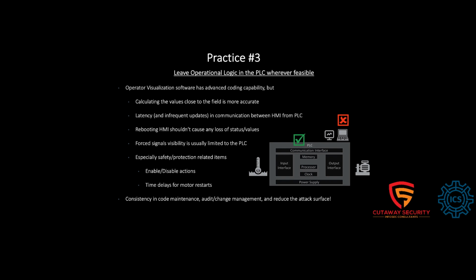It might say, oh, I'm good to start, and then you start, but it hasn't actually started because the PLC has some logic forced against the start. Similarly, enable, disable actions, anything that's safety related, it's better off to be in the PLC itself, especially if you have a time delay for a motor restart or something like that. If you have that in the HMI, but the HMI is not updating frequently or some issues, you don't want an impact on the motor.